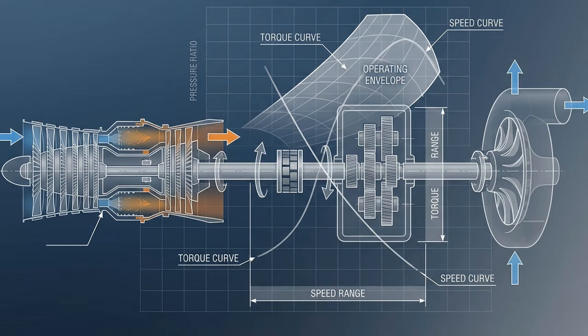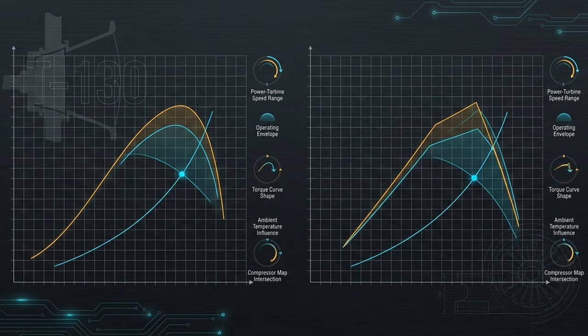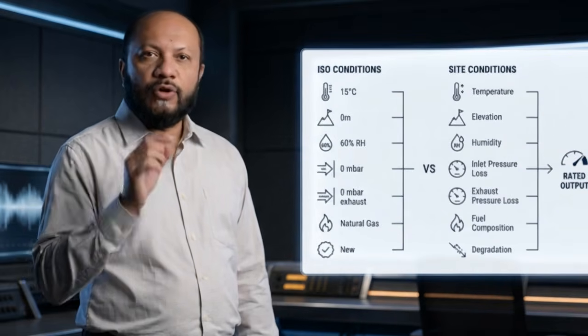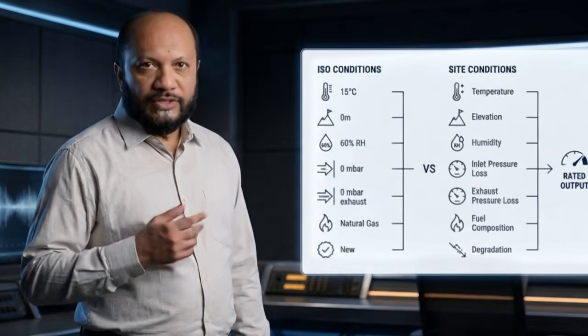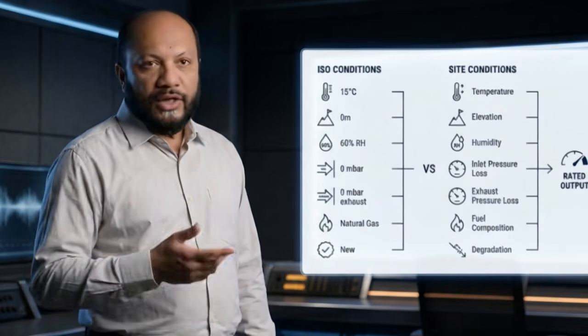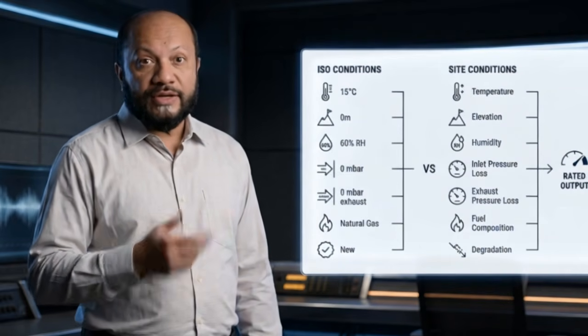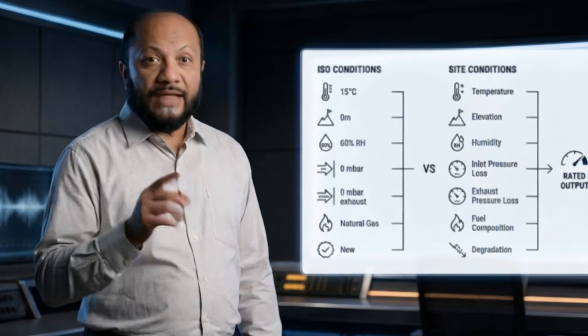For compressor drive service, shaft power alone is not enough. Engineers must check output speed, allowable speed range, torque, coupling arrangement, gear requirements, and the compressor map. The turbine and compressor must work together across the operating envelope. Two turbines with the same megawatt rating can behave very differently on the same compressor. Power turbine speed range, torque curve, ambient temperature, gas composition, and the required station flow can shift the real operating margin. Published ratings are usually based on ISO or reference conditions. Actual site rating changes with temperature, elevation, humidity, inlet pressure loss, exhaust pressure loss, fuel composition, degradation, and operating restrictions. Site derating must be calculated, not guessed.